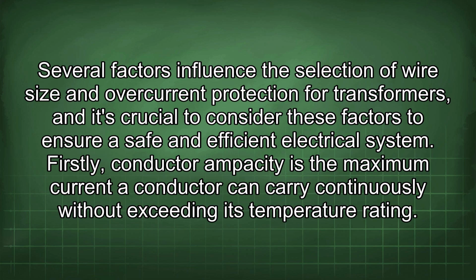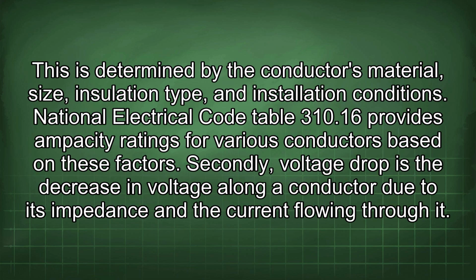Several factors influence the selection of wire size and overcurrent protection for transformers, and it's crucial to consider these factors to ensure a safe and efficient electrical system. Firstly, conductor ampacity is the maximum current a conductor can carry continuously without exceeding its temperature rating. This is determined by the conductor's material, size, insulation type, and installation conditions. National Electrical Code Table 310.16 provides ampacity ratings for various conductors based on these factors.